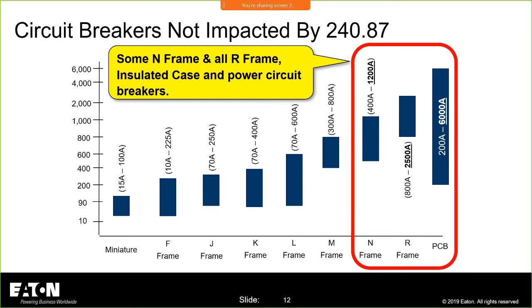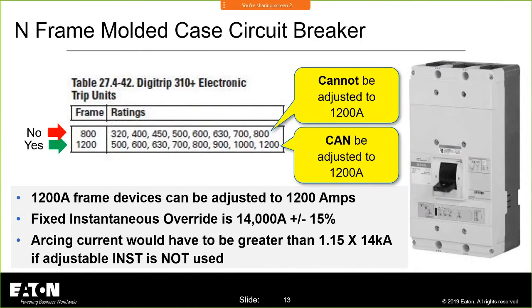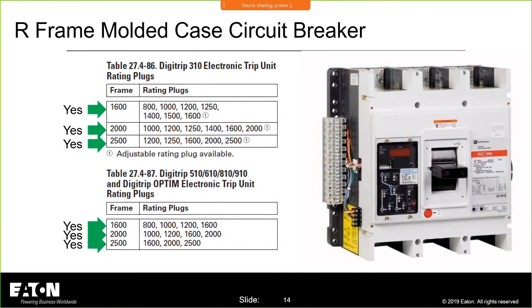N-frame, R-frame, and power breakers, those things can be adjusted up to 1200 amps. If I look at our N-frame breaker, this is an example. I have an 800 amp frame breaker that can be adjusted down to 320. I don't need an arc reduction because I cannot take that N-frame breaker up to 1200 amps. I have to physically change the breaker itself. But the 1200 amp frame breaker can be adjusted down to 500 amps, and I can still adjust it up to 1200 amps. I need an arc reduction technology in that breaker. Power breakers, or I'm sorry, this is the R-frame, still a molded case circuit breaker, goes up to 2500 amps, and all of those can be adjusted to 1200 amps and above.